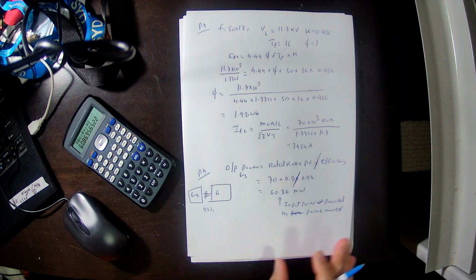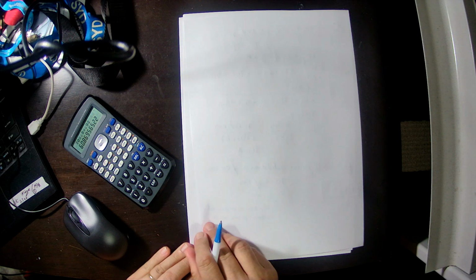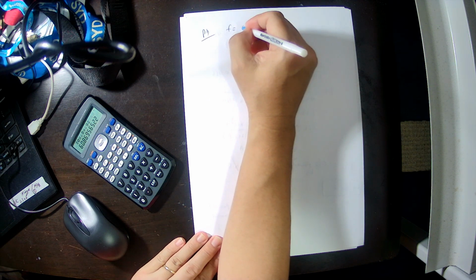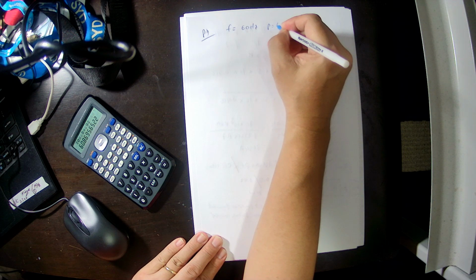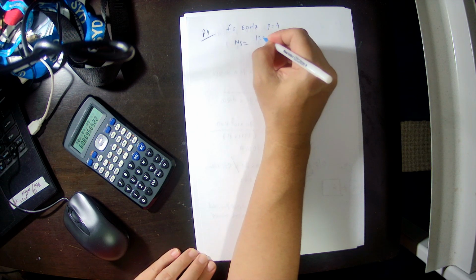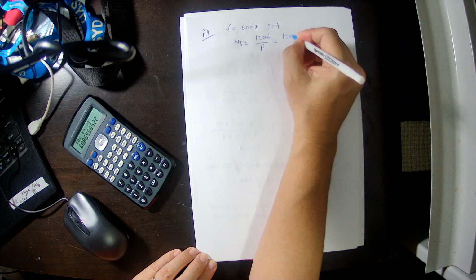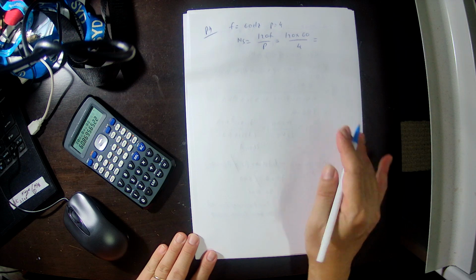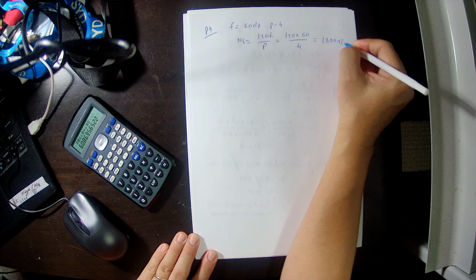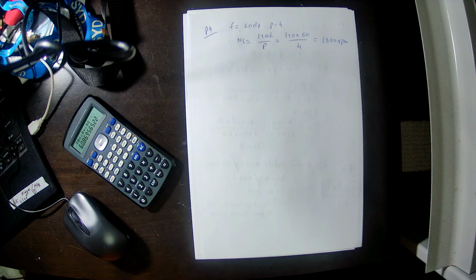Okay, this problem. A 4-pole synchronous motor connected to a supply; determine the speed of the motor. In this case, a synchronous motor, so this is 60 hertz, 4 poles. So Ns can be calculated: 120 f divided by P. 120 times frequency 60, number of poles 4, so we get 1800 RPM. So this is the speed.